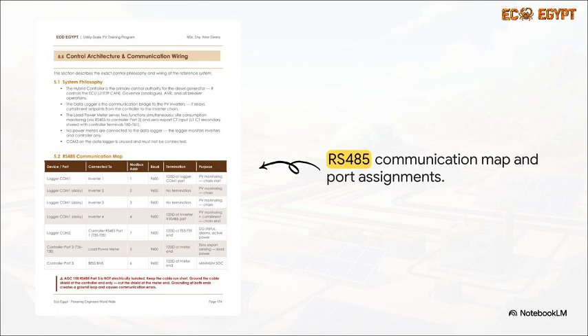But how do these commands actually travel across the site? Check out this single-line diagram and communication map. The data logger is the communication bridge. The load CT detects power flows, sends that to the hybrid controller, which then computes a set point and fires a curtailment command to the logger via RS-485 Modbus. The logger relays it down a daisy chain to all the inverters. The whole system can drop generation to match the load in a blazing fast 200 to 500 milliseconds.